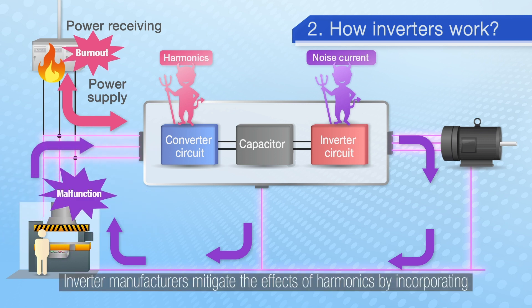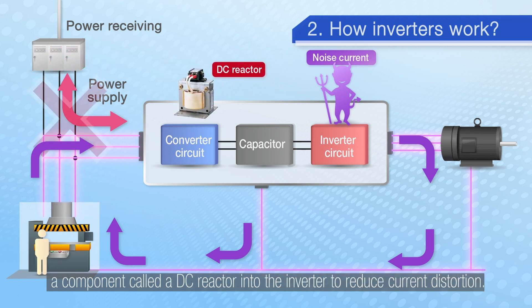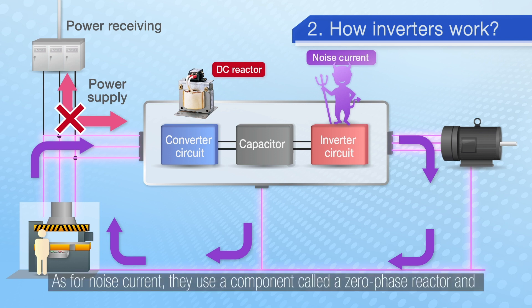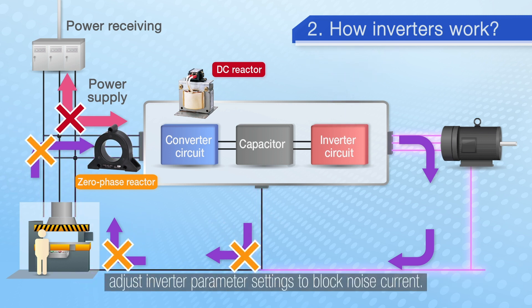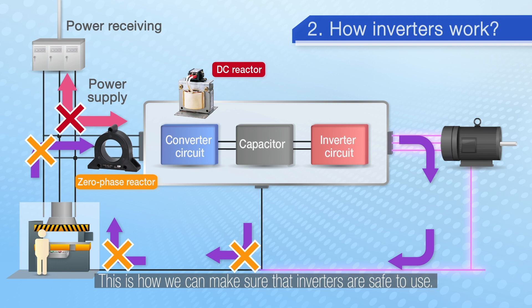Inverter manufacturers mitigate the effects of harmonics by incorporating a component called a DC reactor into the inverter to reduce current distortion. As for noise current, they use a component called a zero phase reactor and adjust inverter parameter settings to block noise current. This is how we make sure that the inverters are safe to use.